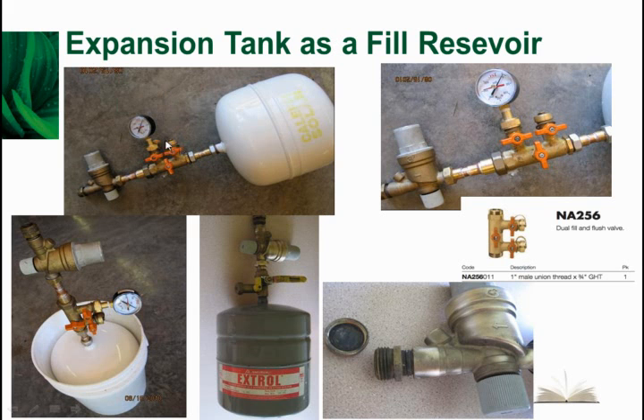And now what you can do is just at your shop pump the fluid that you want to take out, or the cleaner, the inhibitor, the chemical, whatever you're doing on your job, and pump it in there. You can pump 3, 4, or 5 gallons in there depending on what size tank you buy. Put an autofill on there to regulate the pressure. And now just take it out to the job and just hook it right up to the fill connection on there and just leave it on there. What's nice about this, you can leave it for a couple days so you're sure all the air purges out of the system. Go back in a couple days, take it off, and take it back with you.